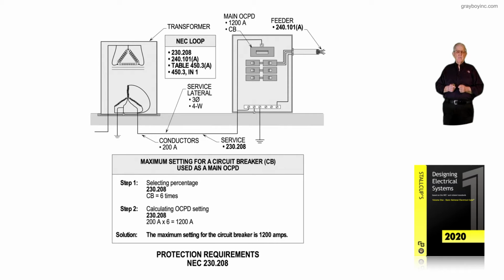This illustration deals with protection of conductors in accordance with 230.208. This is basically what the industry calls the 6 times rule. Notice that those conductors from the secondary side of that transformer routed over and connecting to the terminals or lugs of the overcurrent device, the circuit breaker, is 1200 amp rated.